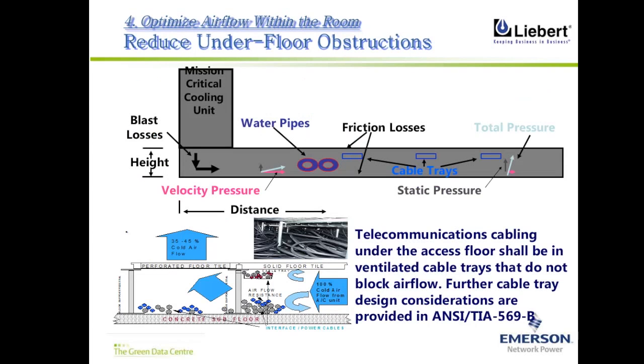Again, this is the biggest problem and biggest challenge when we do refurbishment or quality check of a system or data center which is already installed, because the growth of a data center happens in a haphazard way. A lot of things go below the floor. Sometimes even the tile comes up because of the pressure of the service equipment. You can see the cable trays, water pipes, a lot of infrastructure, structured cabling, and power cable going below the floor.